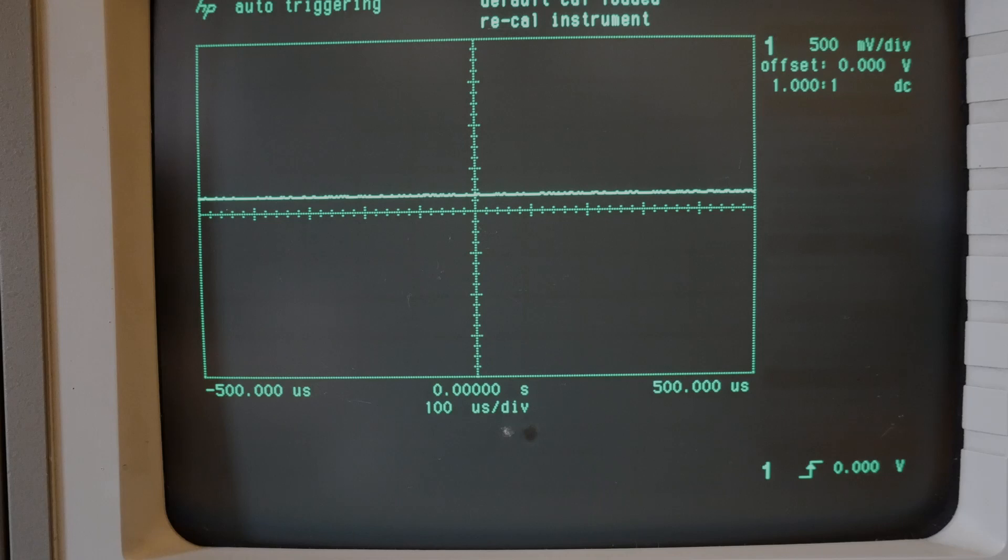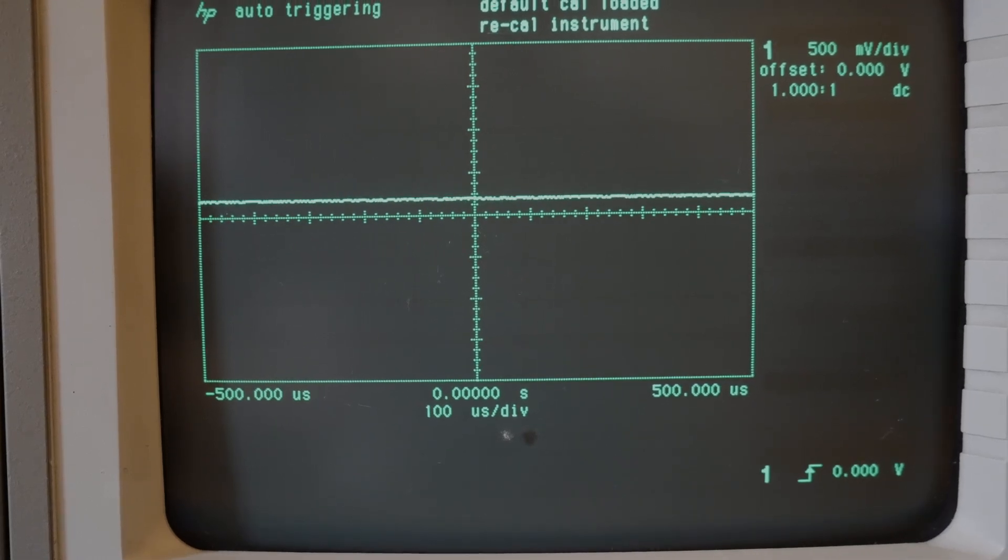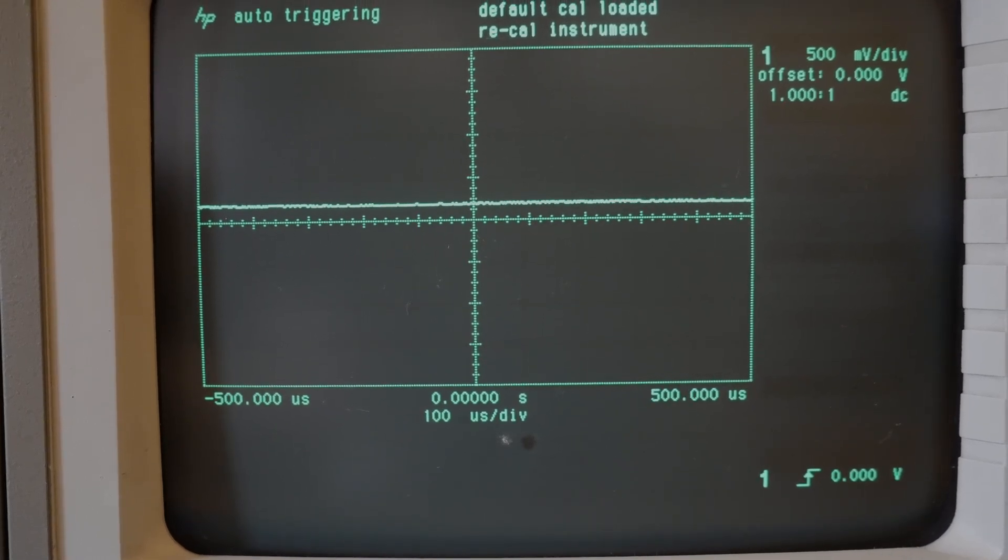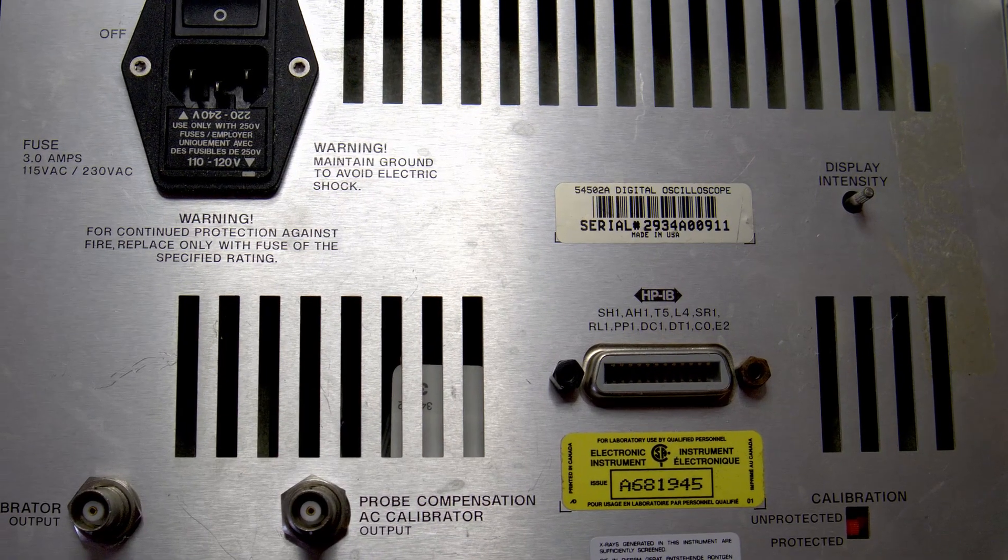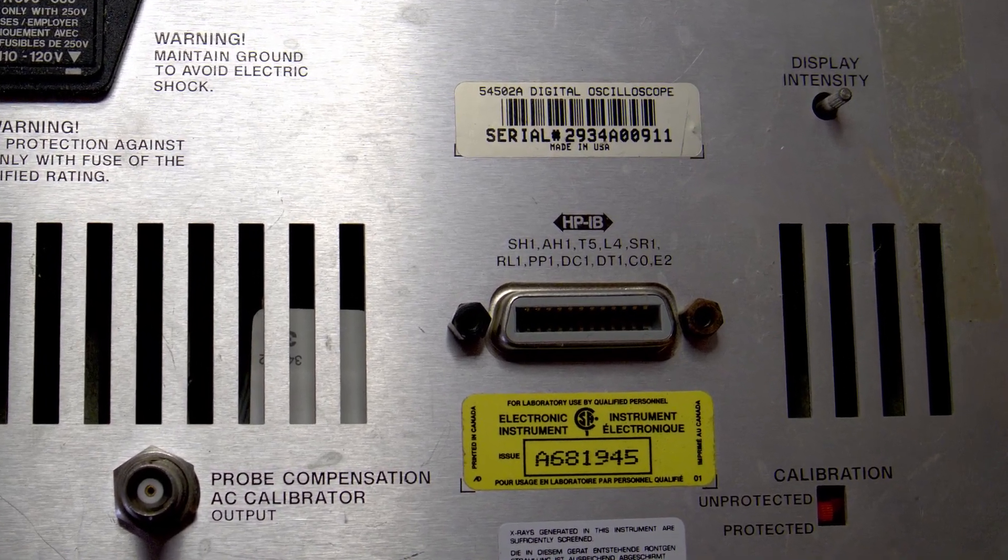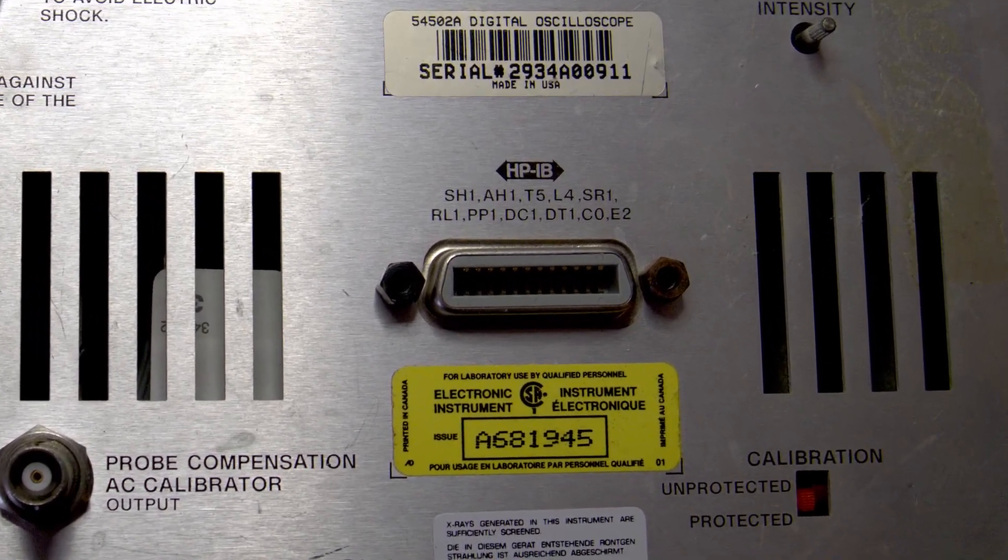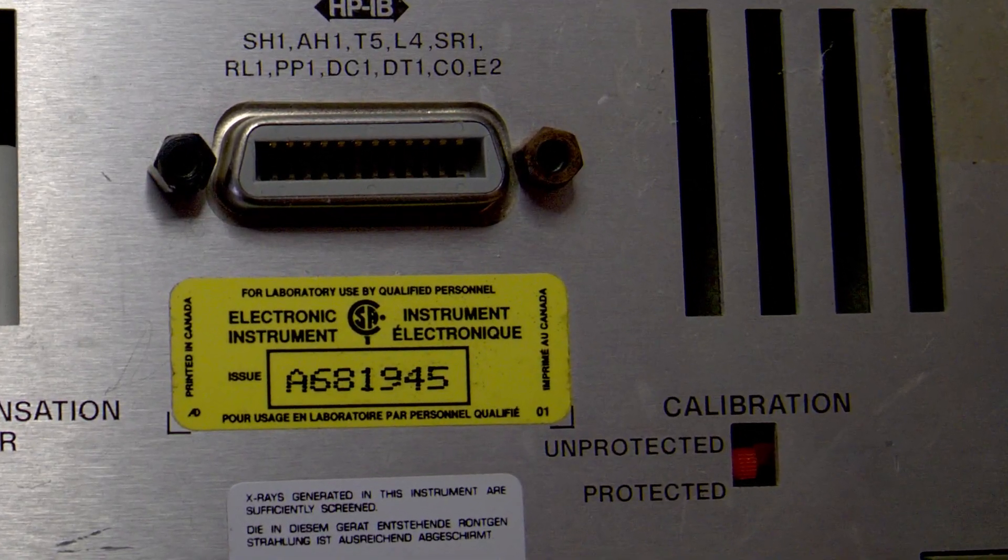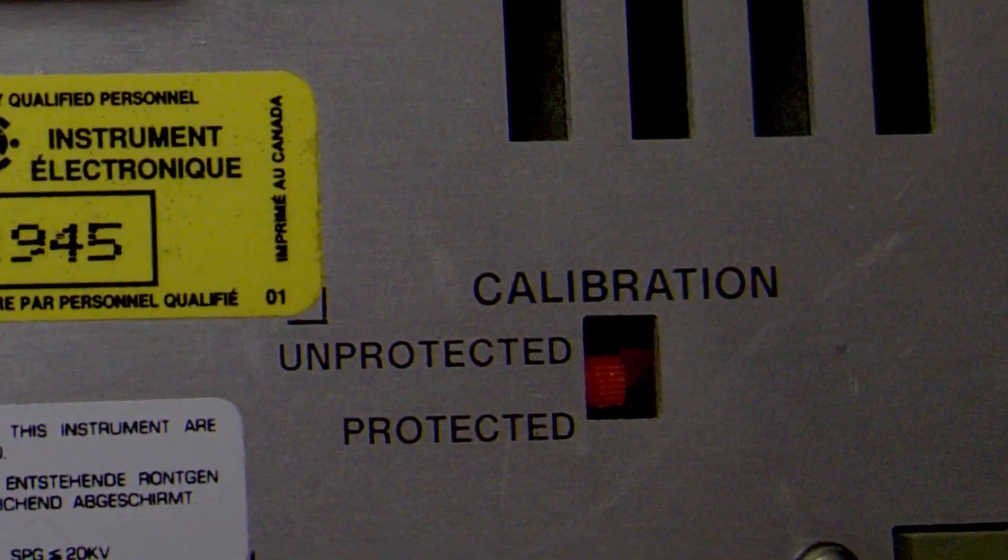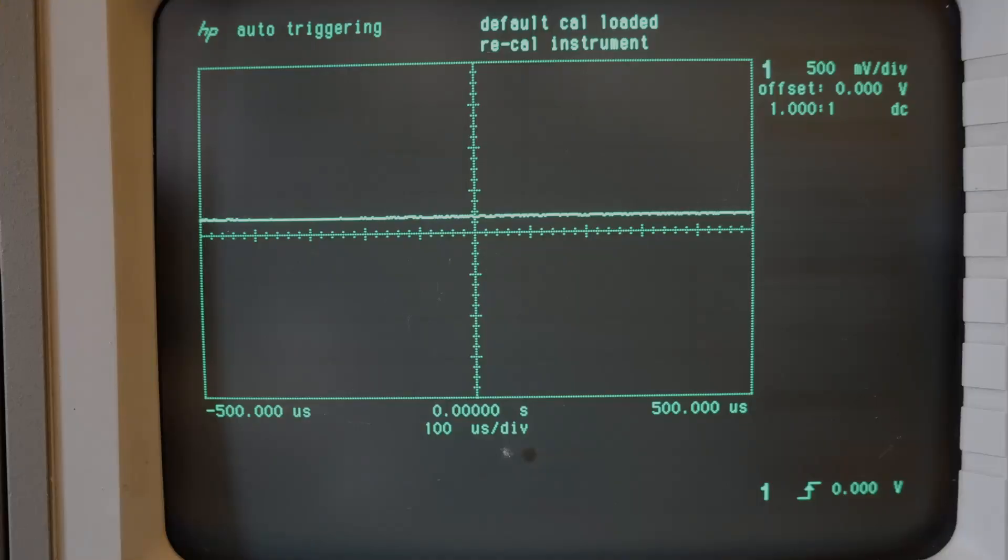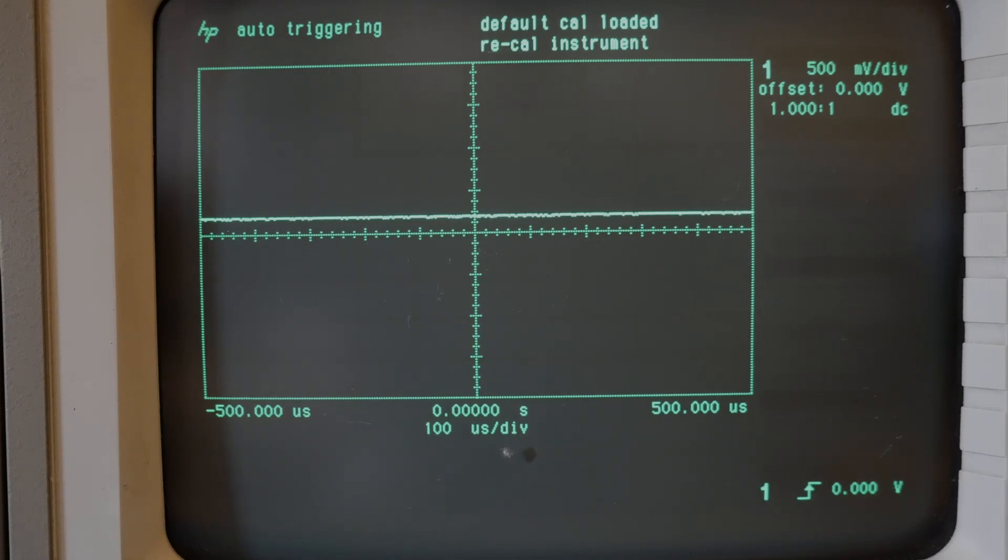Okay so as the first step in the calibration I have turned off the calibration protect switch on the back of the unit which you can see here, and now you can see that the default Cal was loaded and that stopped that waveform from jumping around apparently.